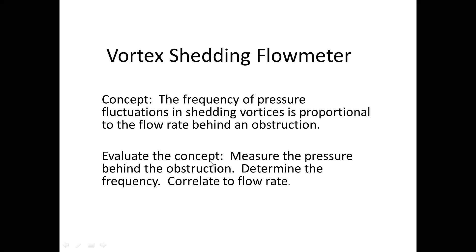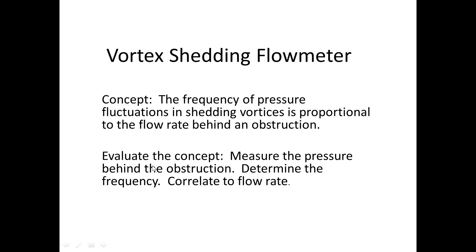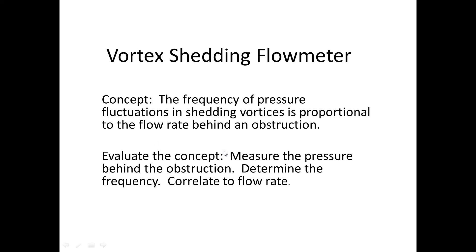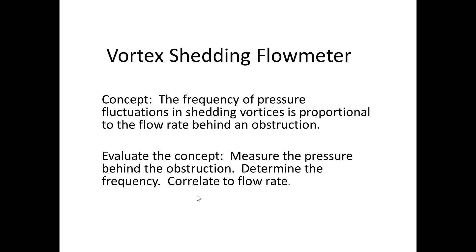If you measure the pressure behind the obstruction, it will fluctuate and vary with time periodically. You could then correlate the frequency of that pressure fluctuation to the flow rate. If this process were to work, you should have a good correlation, and that's essentially how a vortex shedding flow meter works. So imagine that you had an idea for a vortex shedding flow meter and you wanted to evaluate it.